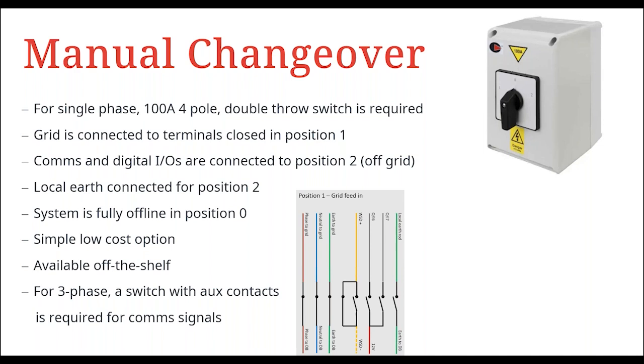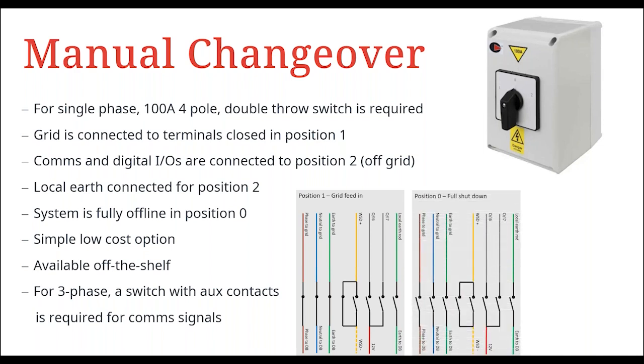What happens is when we switch into the 0 position, we open all of the poles, we open circuits so that we're disconnected from the grid. We're also disconnected from our wired shutdown, so that switches the inverter off. And we're also, on the right-hand side, got our digital signals to tell the inverter whether or not to start generating backup. Of course, everything's open, so in 0 position, there's a full shutdown.